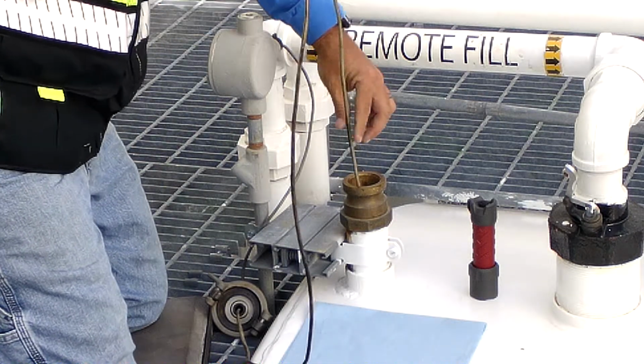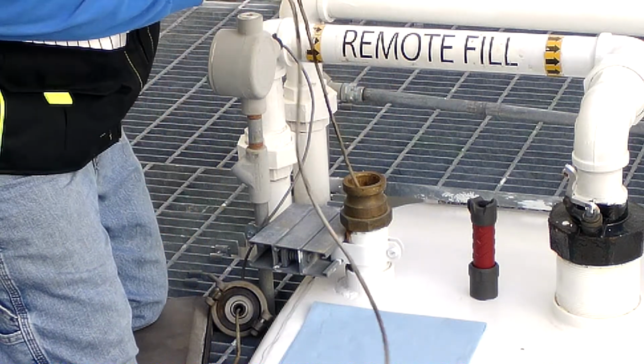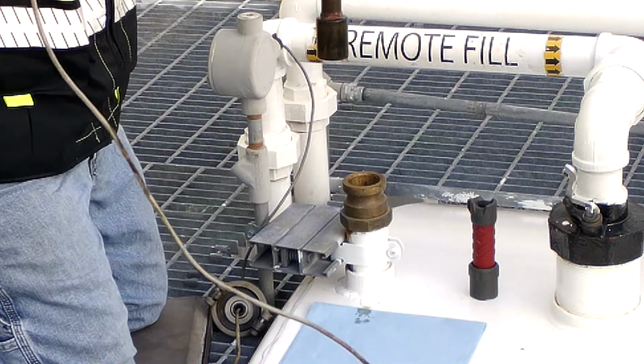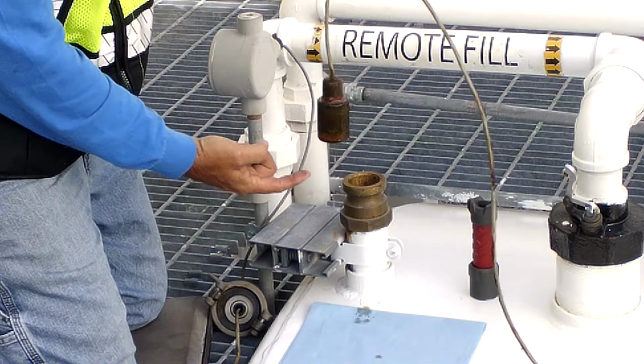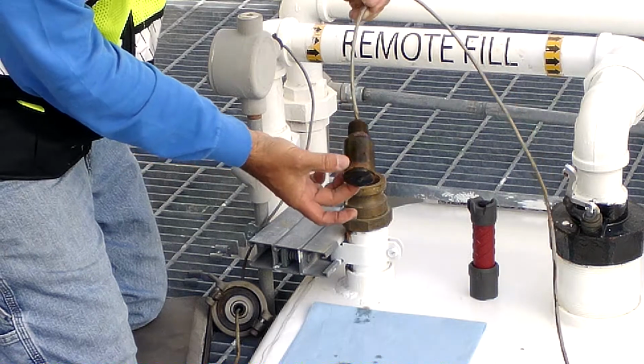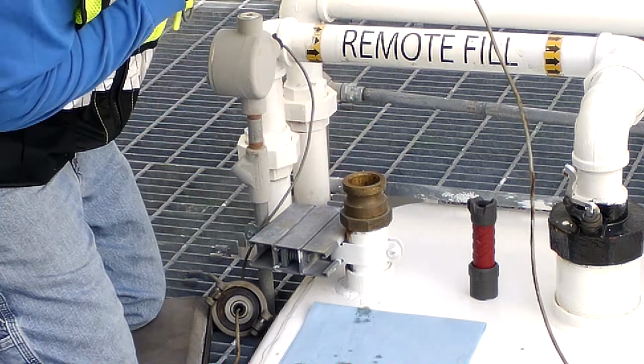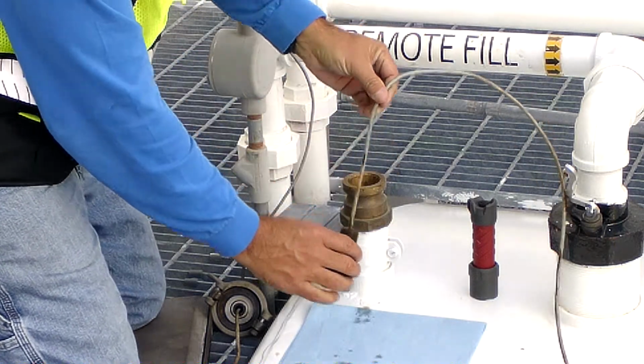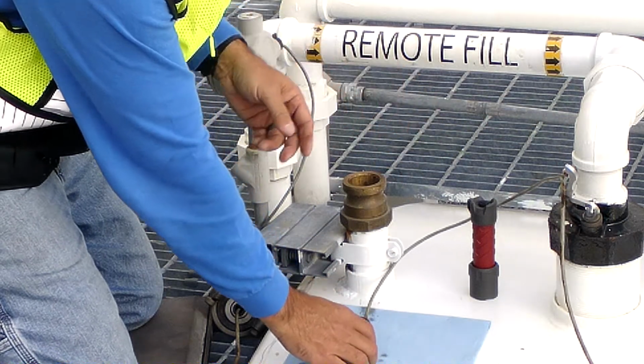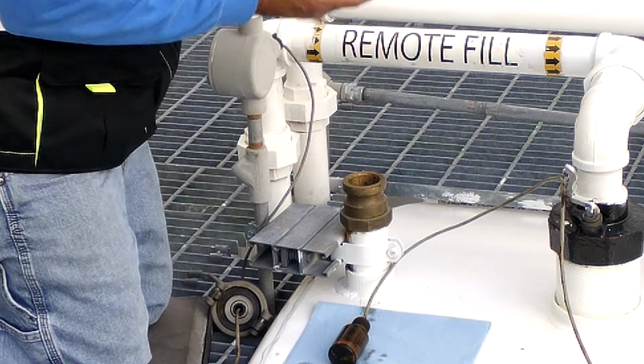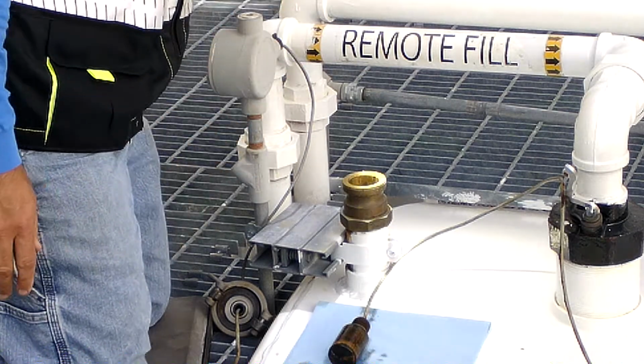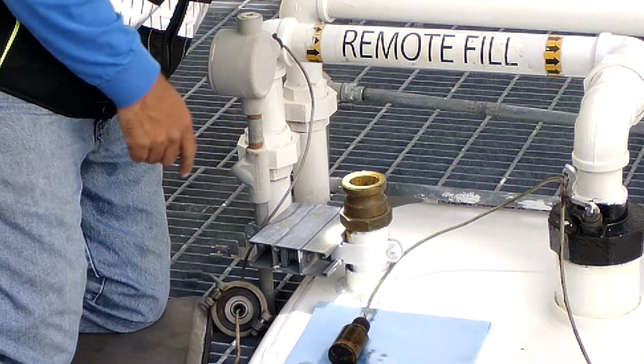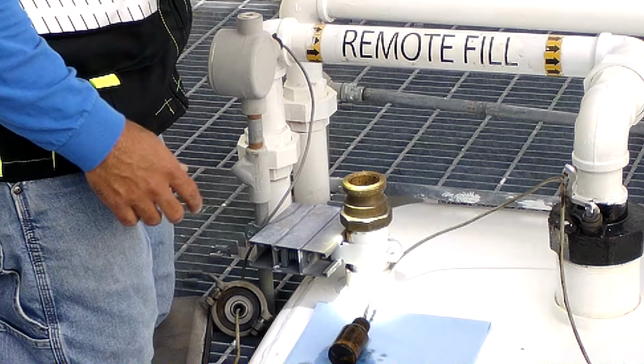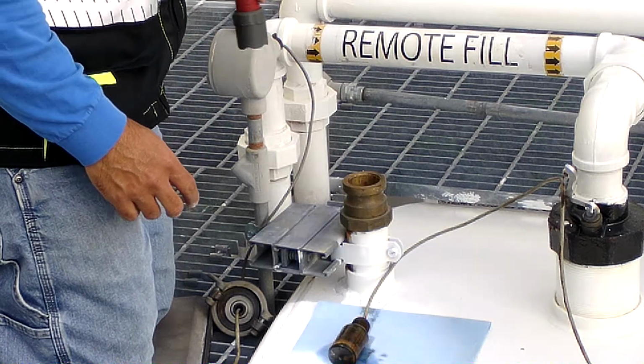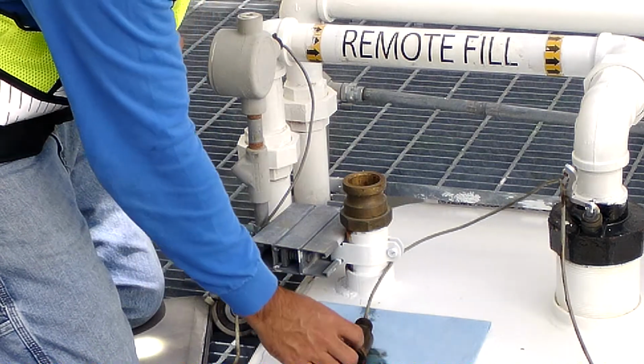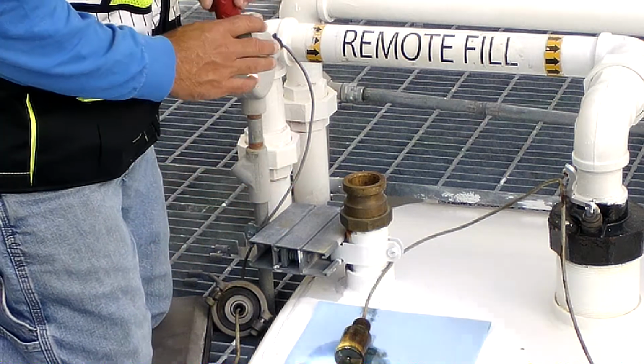Now for this one, I can already hear that there is water, and as I pull this out, you can see a little bit of water dripping from the sensor, and my hands are wet. I can smell it, and it's definitely water. There's no presence of fuel. I take my flashlight, very strong LED, and I can look straight down the riser and definitely verify that there is water in this riser. Again, checking to make sure that there is no fuel, just water.